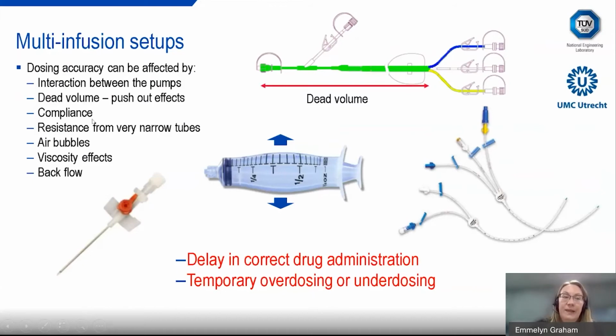We can also get issues with compliance, and if you look at the plastic syringe in the center of the presentation, what can happen is, if you increase the flow rate, because we're dealing with plastic components, the elasticity of these can actually expand. So they'll absorb the increase in the volume from changing the flow rate. So if that's absorbing that, it's not pushing out the drug at a higher flow rate instantly. There can be a delayed reaction. You can also get resistance from very narrow tubes if you've got catheters or other devices. That can cause resistance issues. You can also get air bubbles, you can get viscosity effects, and you can get backflow.